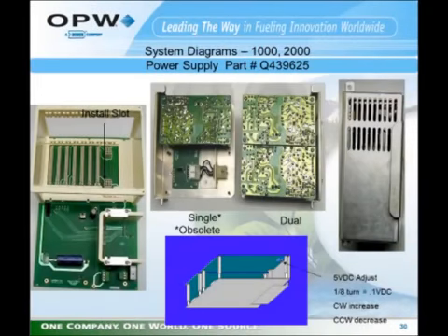The EECO 2000 used to be supported with two power supplies, a single power supply and a dual power supply. The single power supply is obsolete and is no longer used. The single power supply was used in units that only interfaced to probes. We now have a dual power supply. The second half of the power supply in the dual power supply supplies the voltages for liquid sensors and line leak detection sensors.